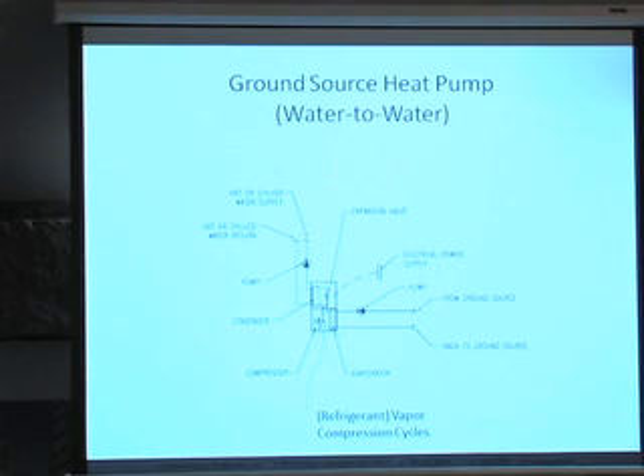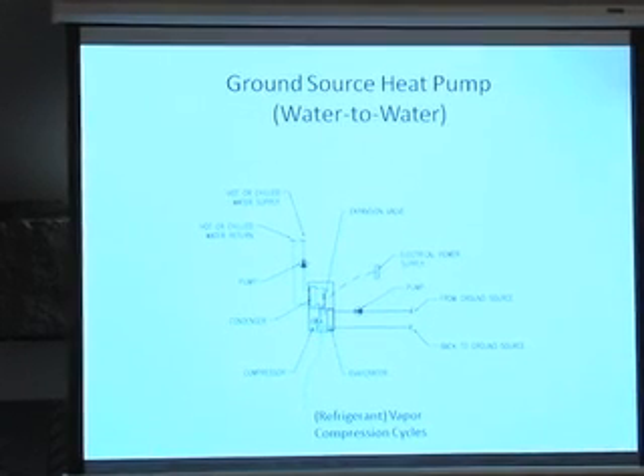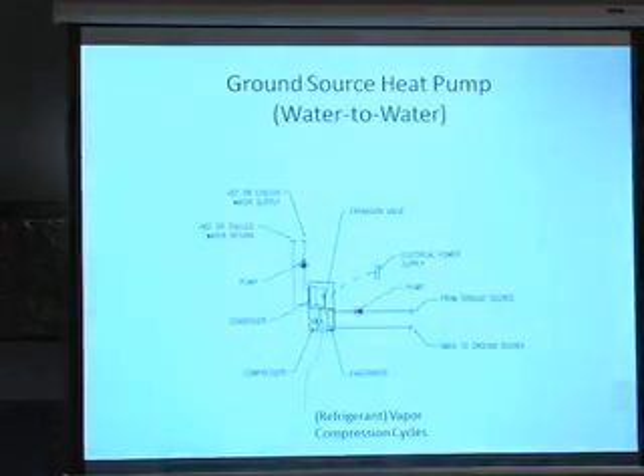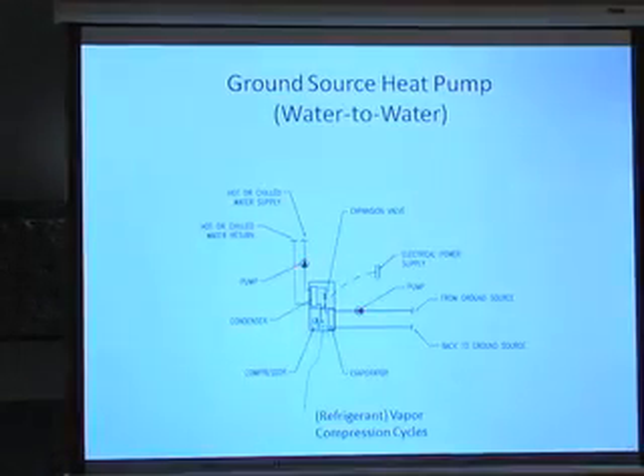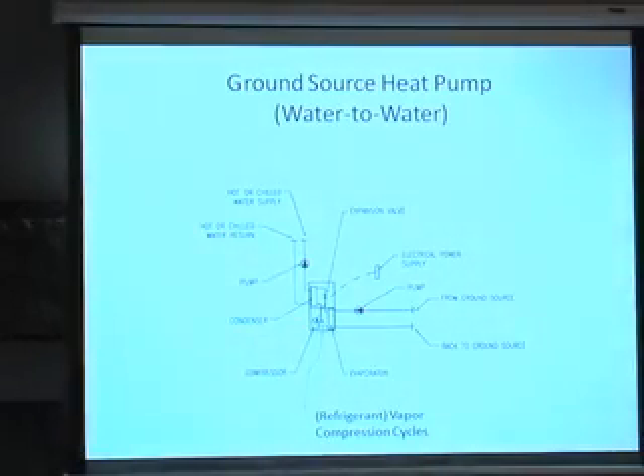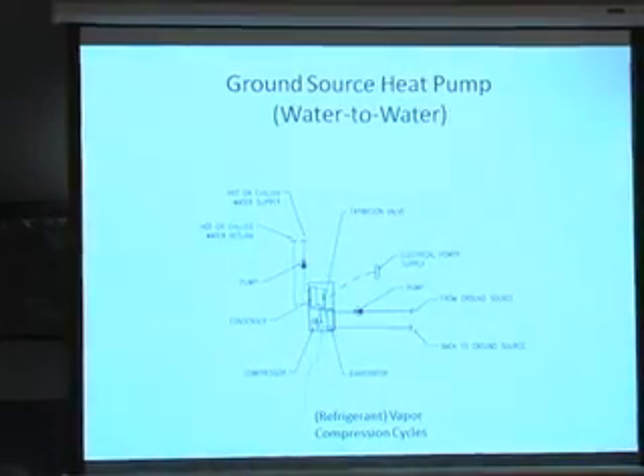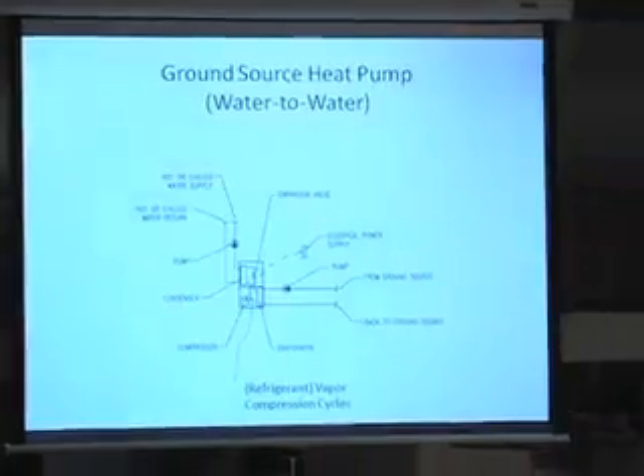This is also a geothermal heat pump. It's a water-to-water. Now, same components inside the casing, same configuration here with the ground loop pump. And instead of producing hot air or cool air, you're producing hot or chilled water that you pump around to fan coil units or whatever air handlers for cooling or heating.